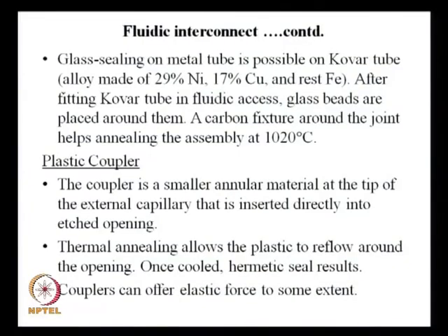So, plastic coupler, if I see what we have written here, it is basically a smaller annular material at the tip of the external capillary that is inserted directly into etched opening. Thermal annealing allows the plastic to reflow around the opening. Once cooled, a hermetic seal results. Coupler can offer elastic force to some extent. So, you understand how a coupler works here.